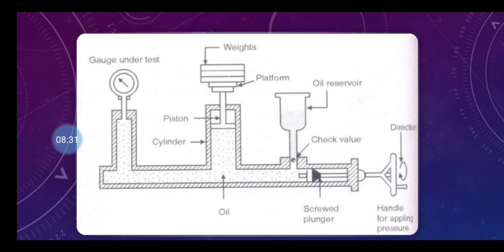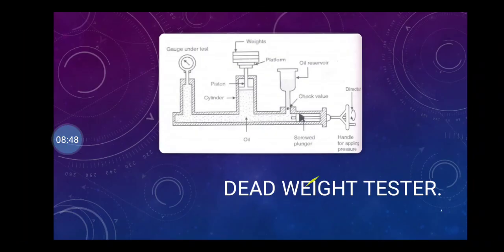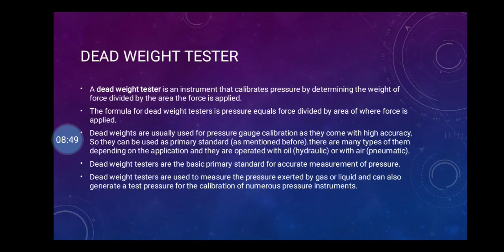Procedure for calibration. Cross sectional view of the dead weight tester is shown in the figure. The handle wheel is turned so that initially oil is allowed to enter into the cylinder. Now a known value of weight is put in the tray. The area of the piston is also known. Knowing this, the pressure is calculated.